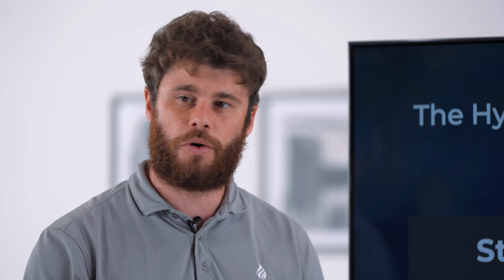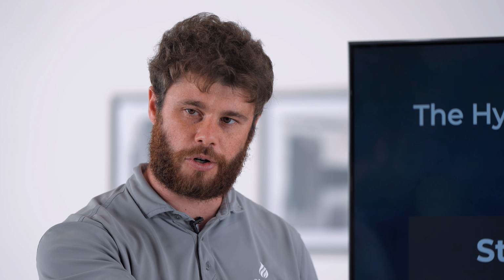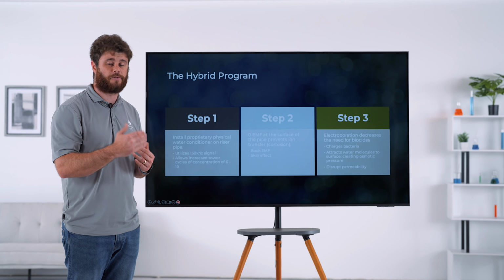So when we install the hybrid program at your facility, we don't just snap our fingers and double cycles and reduce chemicals to 20% of what they once were. It's an iterative process that we work with your on-site team to accomplish. Over 90 days, we will go from current cycles to double your current cycles, and from 100% chemical feed to 20% chemical feed. For the first 30 days, the first month of operation, we'll sit on our hands and keep the system as is. After 30 days, we'll reduce the chemical feed 25% and increase cycles 25%, and so on and so forth, until we are at double your current cycles and 20% of your chemical feed.